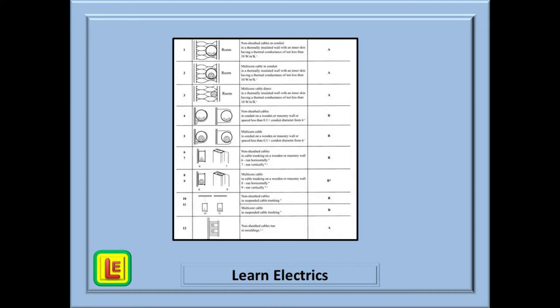If we look at Table 4A2 on pages 386 onwards, we see lots of different reference methods. It is very important that you use the correct reference method when selecting cable sizes, and that you record the correct reference method letter or number on the test certificates. It is part of your job to get it right. At first, the sheer number of reference methods can be intimidating, but we are about to show you a method of looking at them that breaks them down into a very logical and easily memorized system. This is the method that we have taught at Learn Electrics for many years, and we have always found that everyone quickly warms to this method and more easily remembers the correct categories.